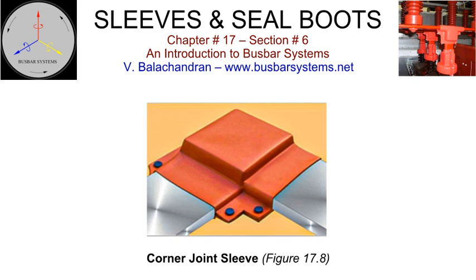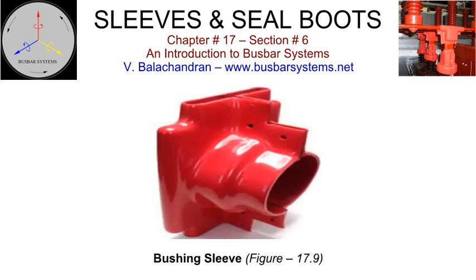There are several varieties of seal boots in one single connection. Most enclosed bus manufacturers, therefore, have an in-house facility for the manufacture of the seal boots. A hollow metallic mold of steel or aluminium of appropriate dimension is made depending upon the shape and size of the joint. It is filled with sand and sealed. Sand helps in storing energy when the mold is heated. The mold is heated to a designated temperature and then dipped in a bath of plastisol for a predetermined time and taken out. Excess plastisol drips back into the bath.